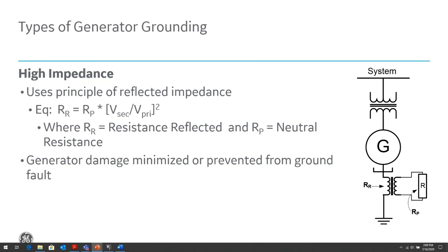Why we do this, obviously, is to limit the ground fault that the generator is subjected to, when there is a ground fault, to very little or practically no ground fault current being seen by the generator. This allows the generator to operate without any damage, but if that ground fault current is allowed to linger for a long time, it can cause damage to the metal over time, and cause some minimal damage, which can lead to evolving from a phase-to-ground fault to a phase-to-phase fault and catastrophic damage. So even though the ground current is very limited, we need to detect those ground faults. And it's very difficult to do, because how can we detect the ground fault when we can't see any ground current? But there are techniques that we will talk about to be able to do that.